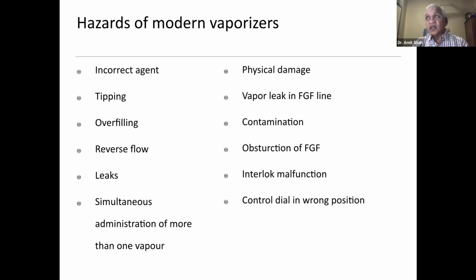It's not that hazards are still not happening. Incorrect agent is still given. Some of them are not tipping proof, so you cannot tilt them. Okay. Some of them have a T mentioned on the dial. If you see T, that is for transport. So when you are transporting a vaporizer from one machine to another machine, you have to put it on the T. And then when you put it on the T, you can easily transfer without tipping it into the anesthetic chamber or a bypass chamber. So tipping can still occur, overfilling can occur, reverse flow can occur, leaks can occur because of the O-ring, because of improper fitting.